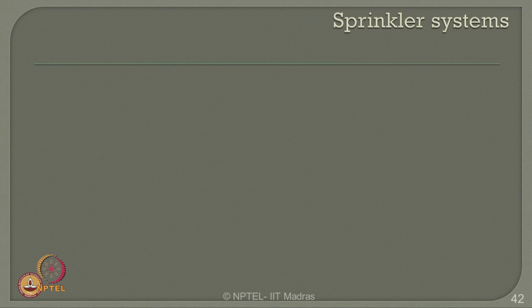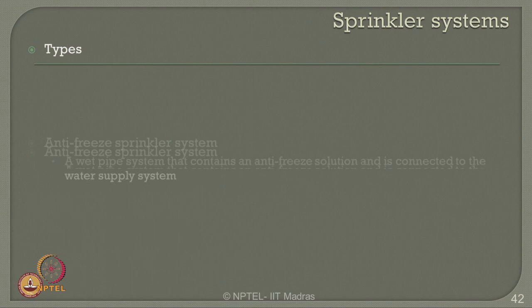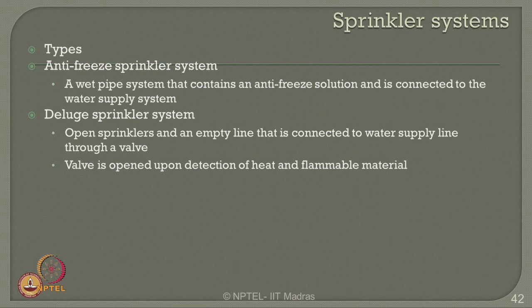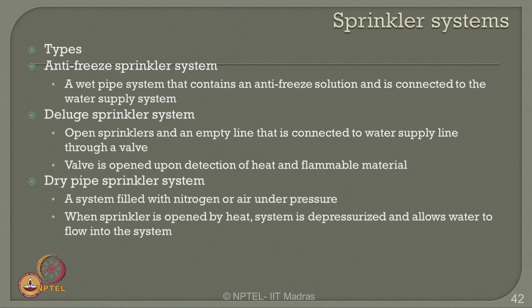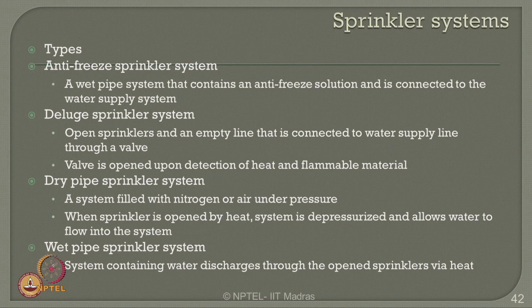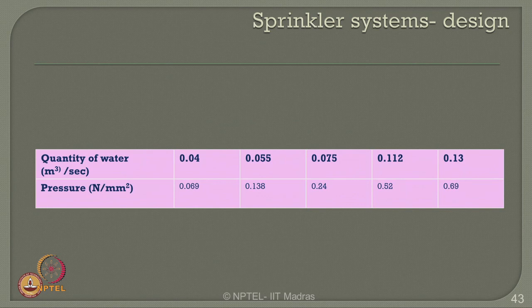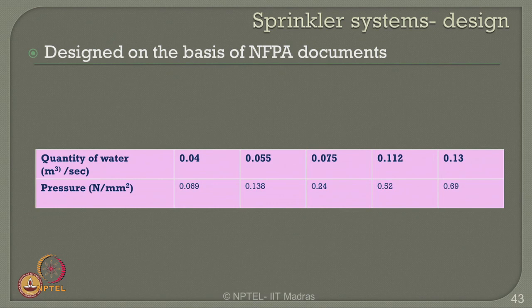Sprinkler systems are also an effective design methodology to prevent or reduce explosion damages. Different types include: anti-freeze sprinkler systems, which are wet pipe systems containing an anti-freeze solution connected to the water supply; deluge sprinkler systems consisting of open sprinklers and an empty line connected to the water supply through a valve opened upon detection of heat; dry pipe sprinkler systems filled with nitrogen or air under pressure, where sprinklers open by heat, the system depressurizes and allows water to flow; and wet sprinkler systems which contain water discharged through open sprinklers via heat.